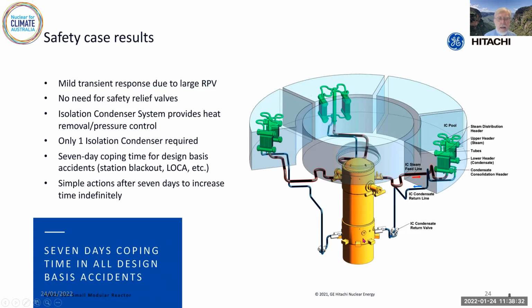Should one of the main lines going off to the turbines break, so you've got a loss of coolant accident and you lose your primary coolant circuit, then a secondary circuit comes into place, giving a thermosiphoning action out of the reactor, back through a condenser, and back down into the reactor itself. There are three of these going through into condensers into this pool. Only one needs to operate to cool this plant down for about 7 days.